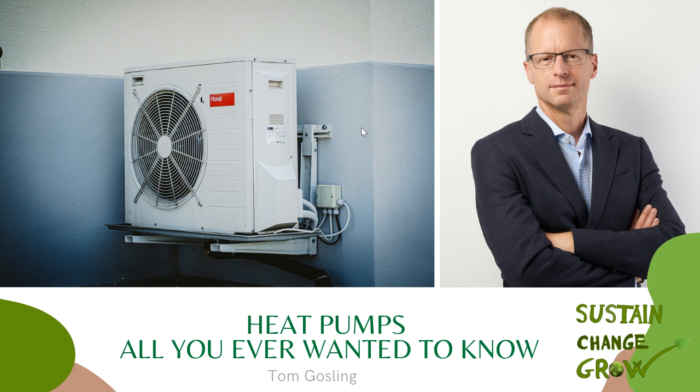And then when you get planning permission, you have to get a noise survey, where they come out and monitor the noise that the heat pump produces compared to the ambient noise. And if the heat pump is above the background noise level, essentially they look at the quietest 10% of periods in a 24-hour period. And if your heat pump makes more noise than that, potentially when it's at maximum, then they can refuse to give you planning permission. And so, the saga we had was that immediately you incur costs by going for planning permission and having to commission a noise survey.